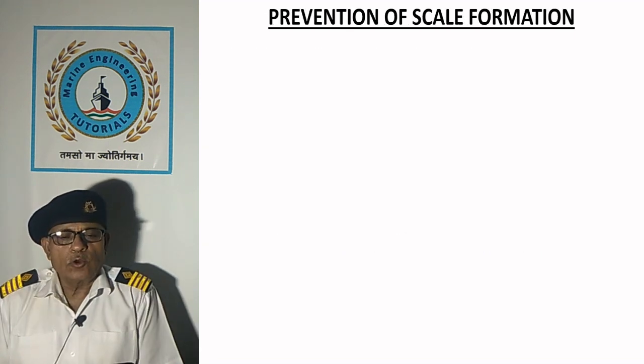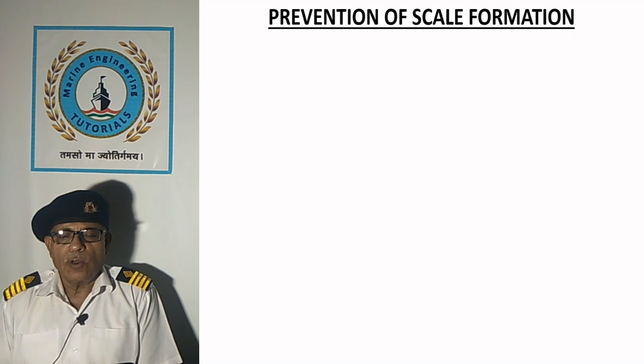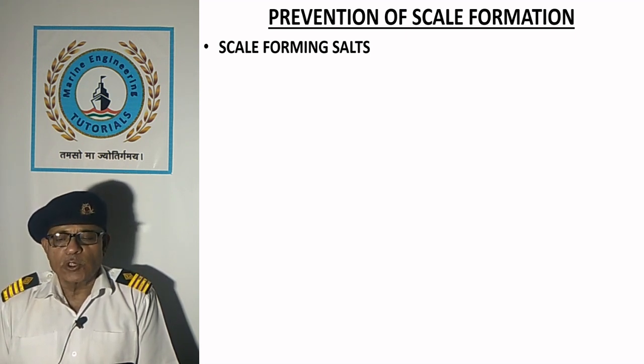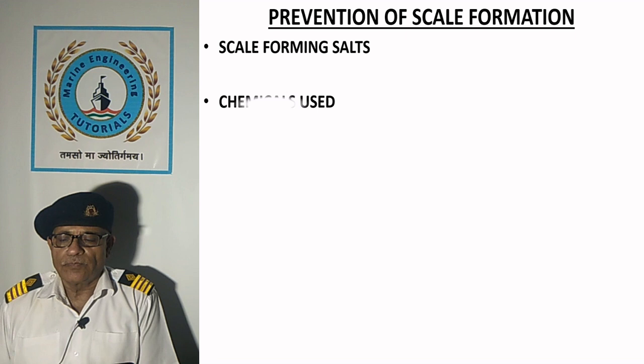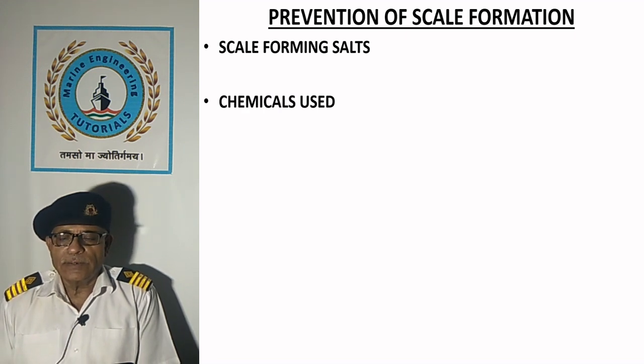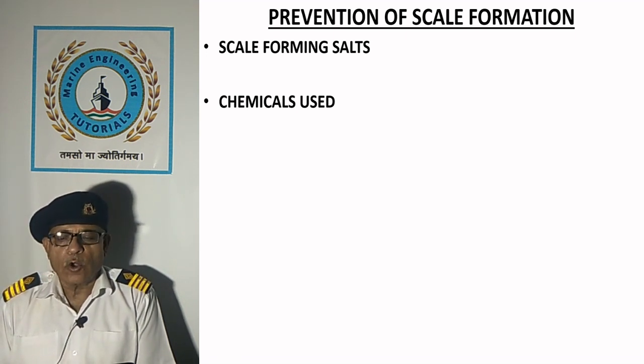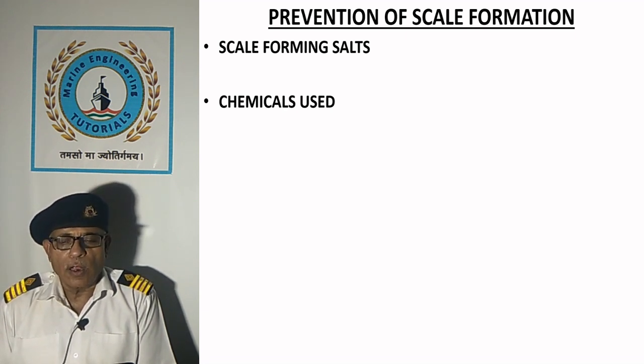Coming to prevention of scale formation: scale-forming salts — calcium sulfate, calcium carbonate and magnesium sulfate — are mainly responsible for scale formation in boilers. In earlier days, lime and soda treatment were prevalent, which have been replaced by phosphate and caustic treatment in modern boilers. Use of phosphate instead of sodium carbonate reduces the amount of caustic soda to be used.